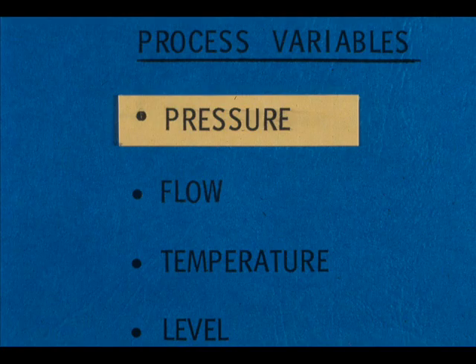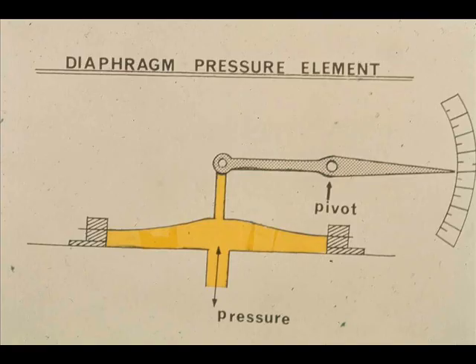Suppose we look first at sensing devices used for measuring pressure. Perhaps the simplest pressure-sensing device is the flexible diaphragm. The diaphragm is subjected to different pressures on each side. The difference in pressures causes the diaphragm to move, which causes a movement of the linkage and a change in the pointer position.